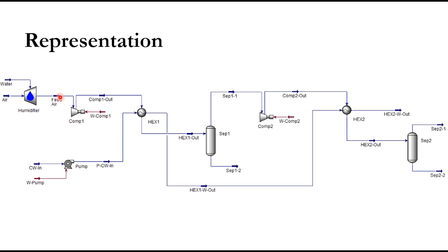If we are assuming the humidity process, we will consider the stream saturator where air is entering, water is fed, and the resulting humid feed air is sent to the first compressor, Comp1. The compressed air exits at high pressure, is cooled using a heat exchanger with cooling water from the cooling towers, then sent to a flash separator where moisture condensate is removed from the bottom. The air stream then moves to the second compressor, is again cooled and passed through another separator.